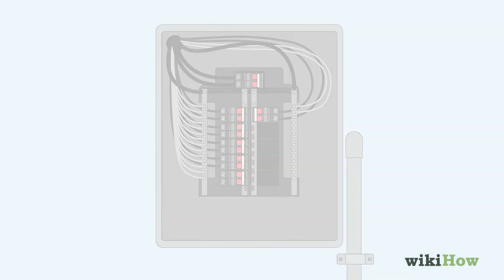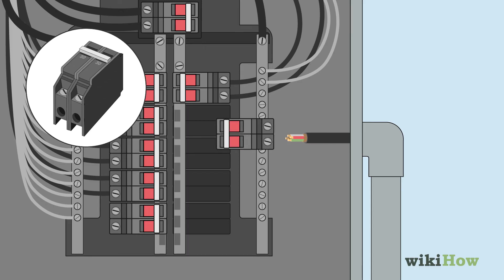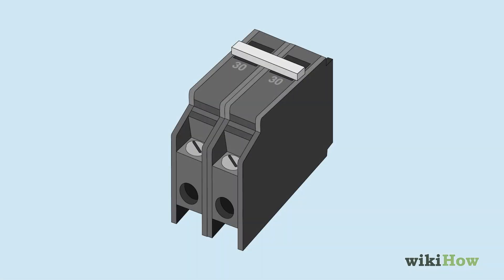Attach a cable clamp to the hole and thread the wires through it. Install a 30-amp double-pole breaker on the circuit, then push the ends of the red and black wires into the ports on the breaker.